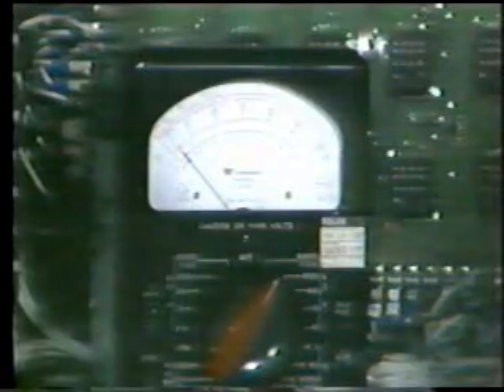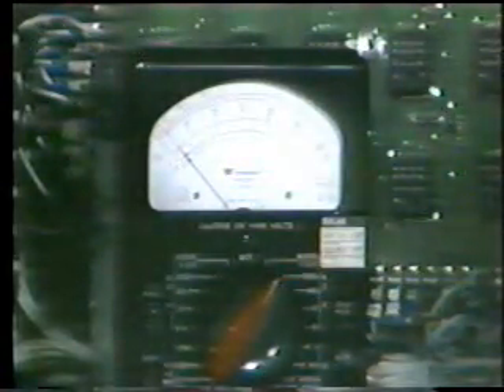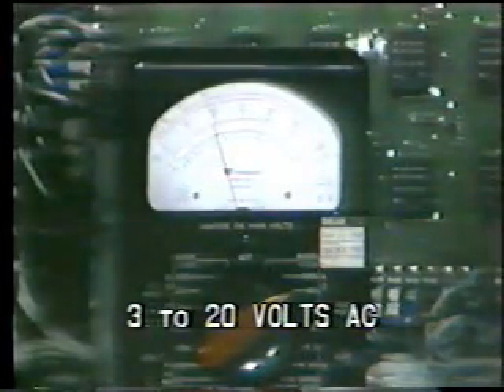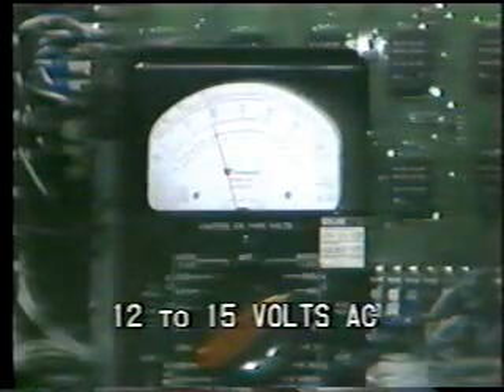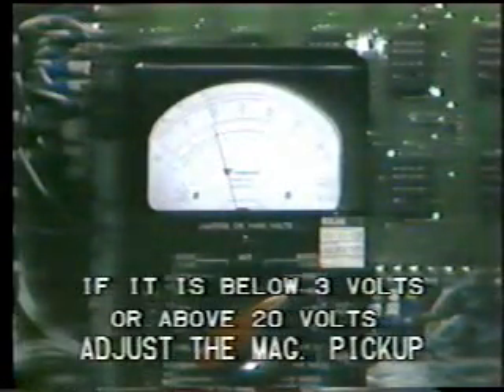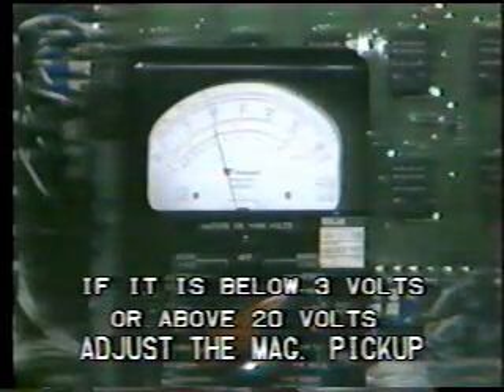Multimeter should read very low. However, if the reading is high, an adjustment must be made. If the voltage is low, continue to switch the scale down until you're able to read the correct voltage. The multimeter read between 3 to 20 volts, and ideally, the output would be 12-15 volts AC. Record the voltage. If it's below 3 volts or above 20 volts, the magnetic pickup needs to be adjusted. Remove the multimeter leads. Warning: the engine must be shut down to adjust the magnetic pickup. Under no circumstances should the engine be rotated while the magnetic pickup is out of the engine gearbox.